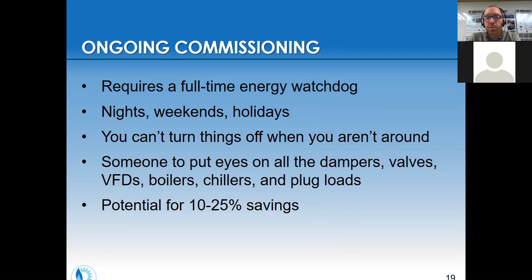The question is, what is really happening when no one's in your library? What lights are on? Is the emergency lighting left on necessary, or could it be reduced? Taking a camera and walking through at 9 o'clock at night can be really interesting, seeing what's still on after everything's shut down, feeling which fans are still blowing air, looking at which dampers are still open. There's potential for at least 10% savings, probably 25% in some buildings. We find buildings that are on 24/7 that didn't realize it.